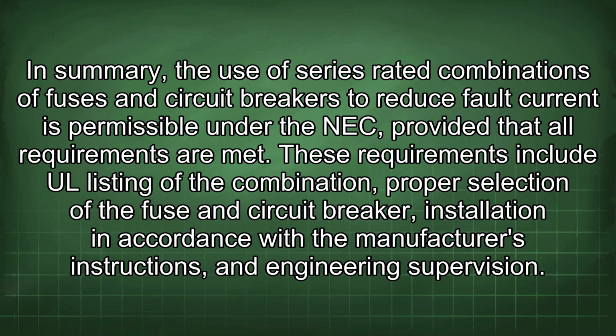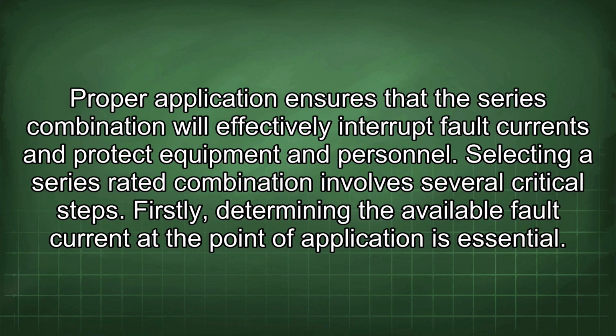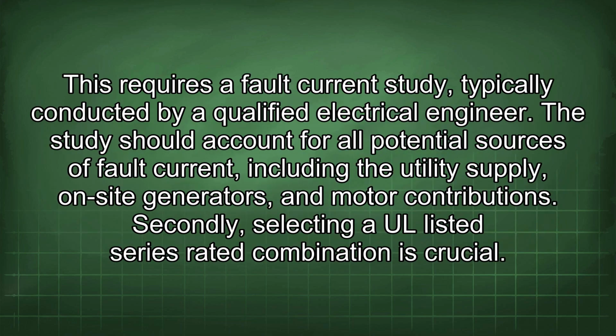These requirements include UL listing of the combination, proper selection of the fuse and circuit breaker, installation in accordance with the manufacturer's instructions, and engineering supervision. Proper application ensures that the series combination will effectively interrupt fault currents and protect equipment and personnel. Selecting a series-rated combination involves several critical steps. Firstly, determining the available fault current at the point of application is essential. This requires a fault current study, typically conducted by a qualified electrical engineer. The study should account for all potential sources of fault current, including the utility supply, on-site generators, and motor contributions.